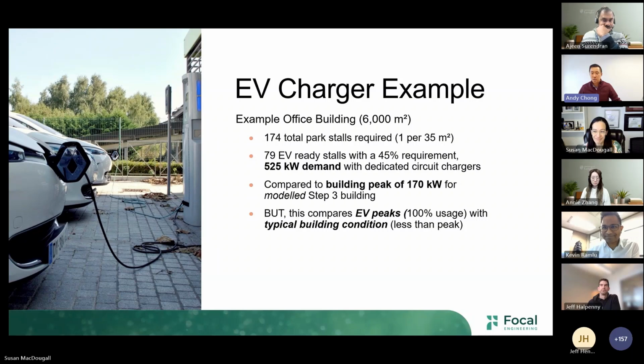Kevin, you have another clarification. Yeah, just a comment - I think this was for level 2 charging, right? So whatever it is, 40 amp or something like that, at some maximum amount, and the calculations here are done in a scenario which may never happen, or might not for a long time. Also want to highlight that as this is being examined across the province, there's probably 100 different ways to slice this pie. It's probably not likely in a lot of regulation moving forward where they'd offer full power to, say in this case, 45% of spots. It's probably going to be 10% of spots with X amount of maybe level 3, a certain amount will have level 2, and a certain amount will have different types of charging.